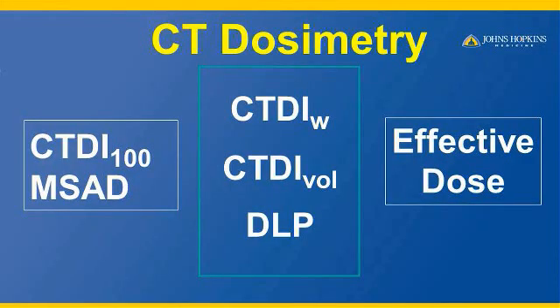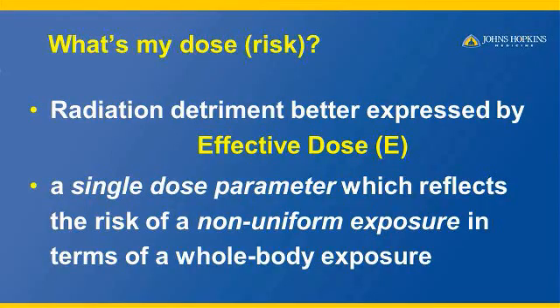When you say patient dose, we normally are interested in estimating effective dose. In order to arrive at the effective dose, we do measurement on what is called the CTDI-100, from which we measure or estimate other dose descriptors, finally arriving at effective dose. Because when a patient asks what is my dose, they typically mean what is my risk. They want an overall risk, which is explained by a concept called effective dose — a single dose parameter which reflects the risk of a non-uniform exposure in terms of whole body CT.